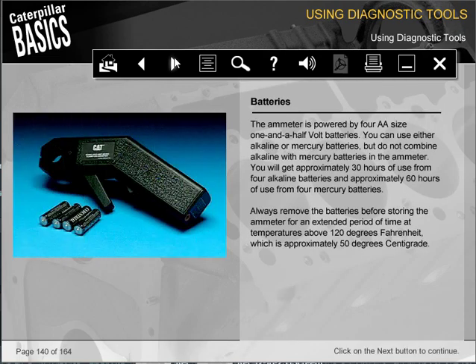The ammeter is powered by 4 AA size 1.5 volt batteries. You can use either alkaline or mercury batteries, but do not combine alkaline and mercury batteries in the ammeter. You will get approximately 30 hours of use from 4 alkaline batteries and approximately 60 hours of use from 4 mercury batteries. Always remove the batteries before storing the ammeter for an extended period of time at temperatures above 120 degrees Fahrenheit, which is approximately 50 degrees centigrade.